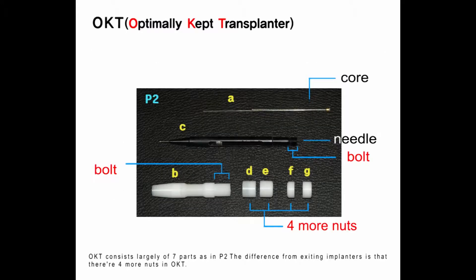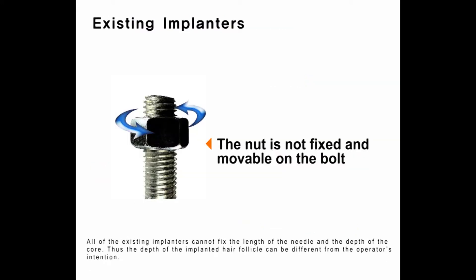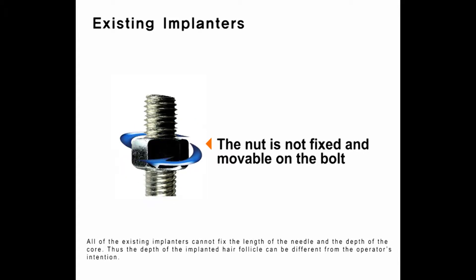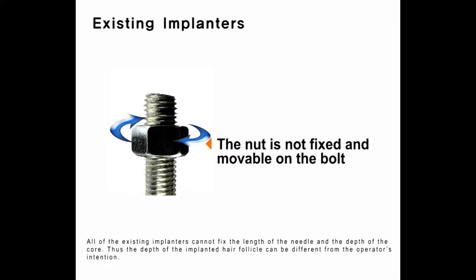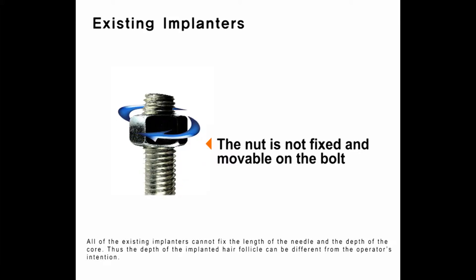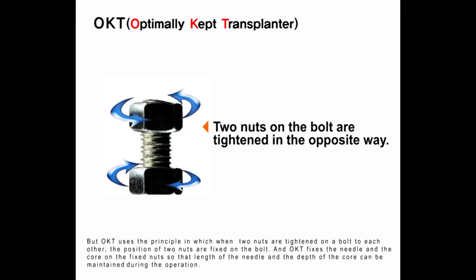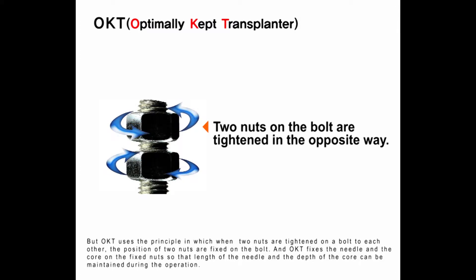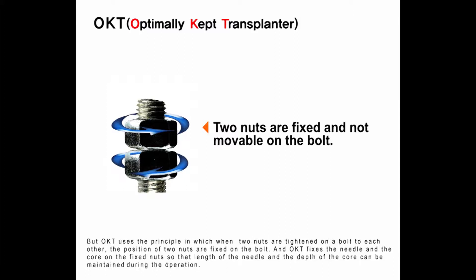OKT consists largely of seven parts. The difference from existing implanters is that there are four more nuts in OKT. All existing implanters cannot fix the length of the needle and the depth of the core, so the depth of the implanted hair follicle can differ from the operator's intention. OKT uses the principle in which when two nuts are tightened on a bolt against each other, their positions are fixed, and OKT fixes the needle and core on those nuts so that the needle length and core depth can be maintained during the operation.